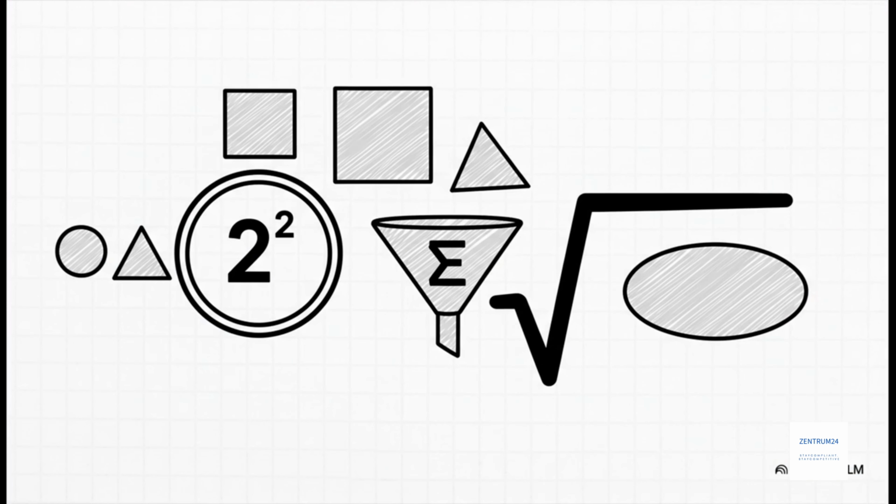So the engine that drives all of this is a method called root sum of squares. It's the standard, statistically sound way to combine different, unrelated sources of error. And the process is simple. You take the uncertainty value for each component, you square it, you add all those squared numbers together, and then you just take the square root of that big sum. And bam! The result is our combined standard uncertainty, UC.